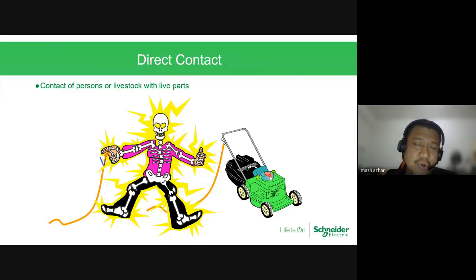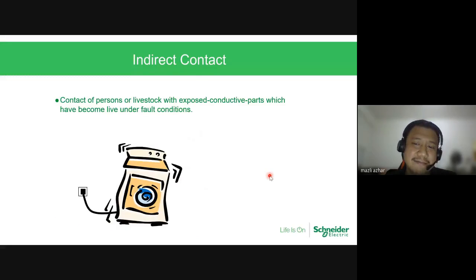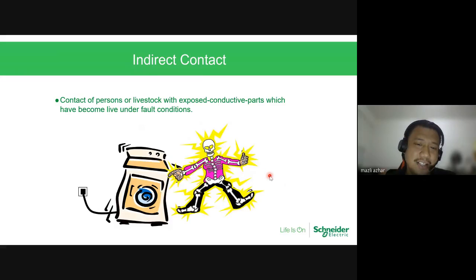Okay. When I say indirect contact, you will see you are touching... Okay, normally this happens like normal. You can see this when you're touching the washing machine, right? So this is where the indirect contact happens. Okay, when there is a leakage or the cable is faulty, the exposed conductive part, you accidentally touch it, then it becomes live under fault condition. This is where indirect contact happens.